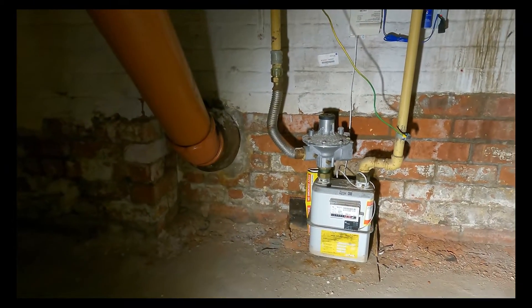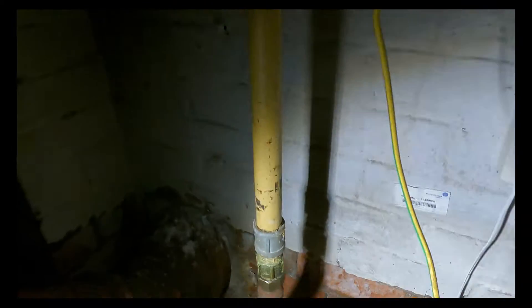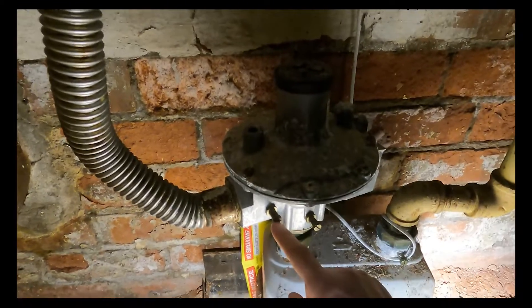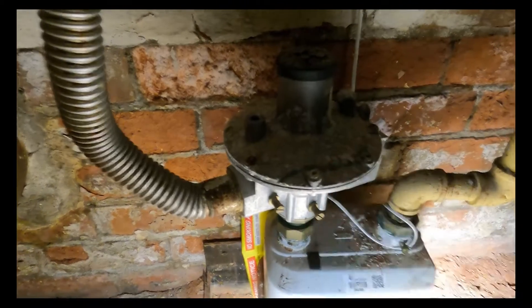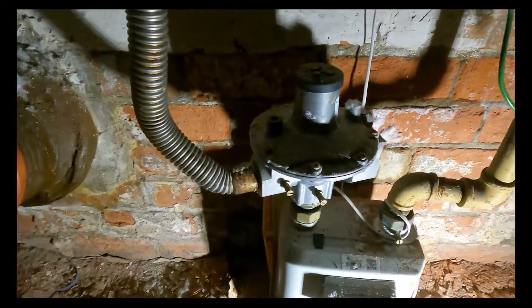Just a bit of a beauty - we've got the control board right over there so we can turn all the power back onto the building. I've got my full apprentice upstairs now just getting the entire cold water main turned on. So looking at this G10 meter, comes down - it's been isolated on the ECV and the old client has actually taken the handle off, so I can get that recommissioned today, get that turned back on. We've got our incoming gas main, our Anaconda regulator. There are two test nipples on these - this tests the incoming pressure, but your local gas network provider would use this one. We wouldn't use this as gas engineers because this part of the meter from here is actually the gas provider's.